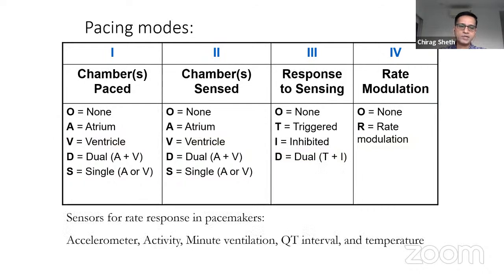So for rate modulation, the devices are equipped with certain functionalities which are inbuilt in the system. There are accelerometers, sensors for activity, sensors for minute ventilation, sensors which look at QT intervals, and of course body temperature. Based on changes in these parameters, the sensors guide the device to increase the heart rate so that the patient can have a rate responsiveness to physical activity.